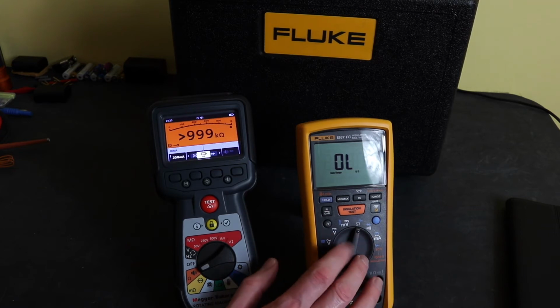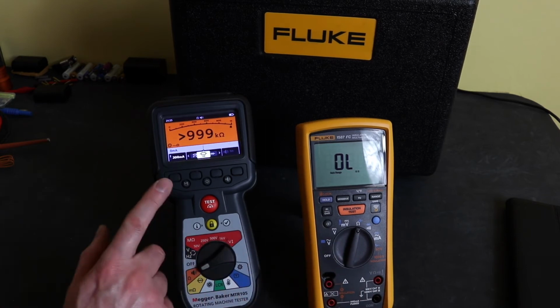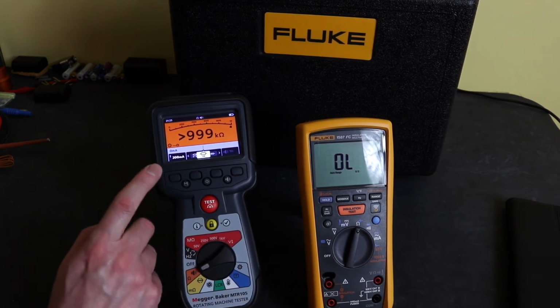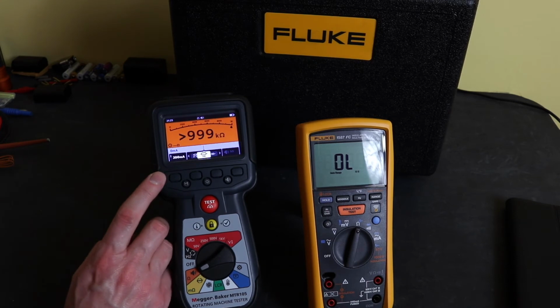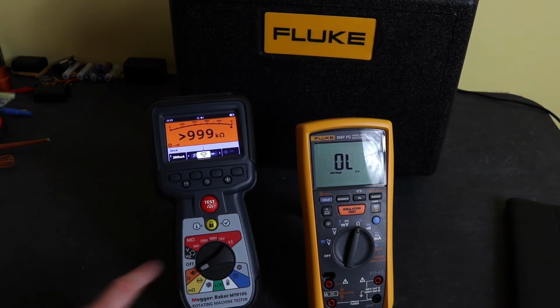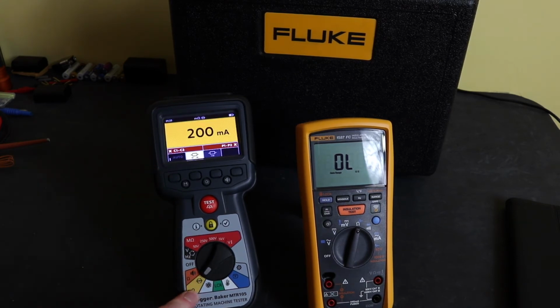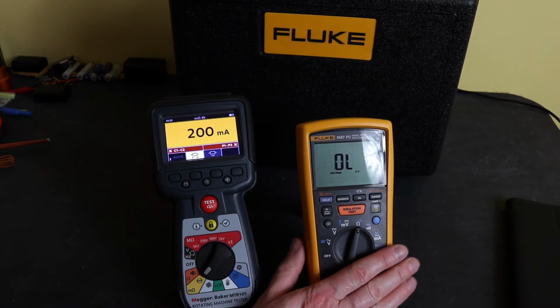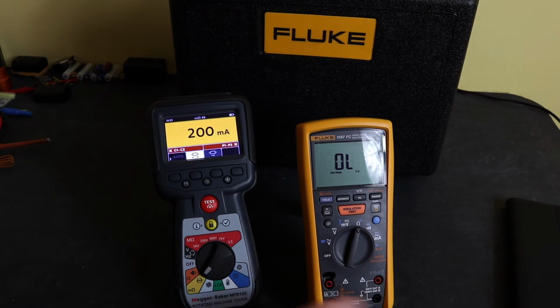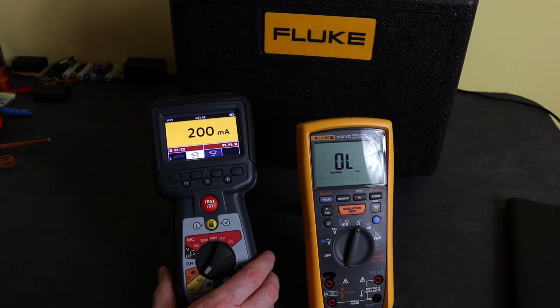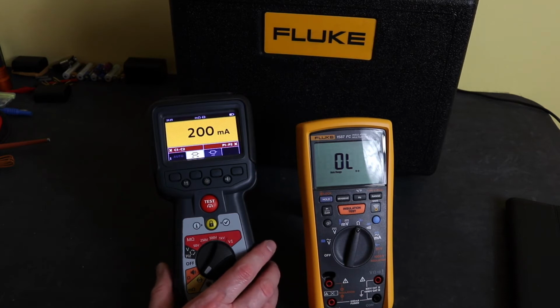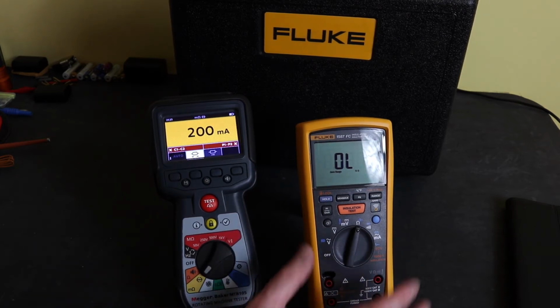Test current is around about 1 milliamp, so I will always opt for the 200 milliamp. It's actually a requirement to UK standards for earth continuity testing. As well as the standard resistance, the MTR105 has its 4-wire measurement, which this has nothing to compare against. So you will get much better measurement of motor windings, transformer windings with the MTR105 than you will with 1587, really.